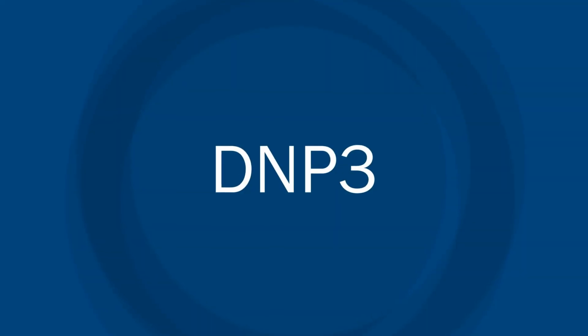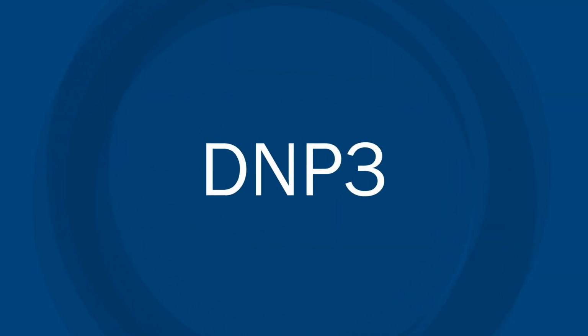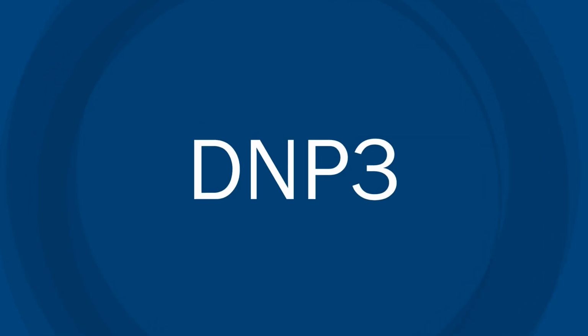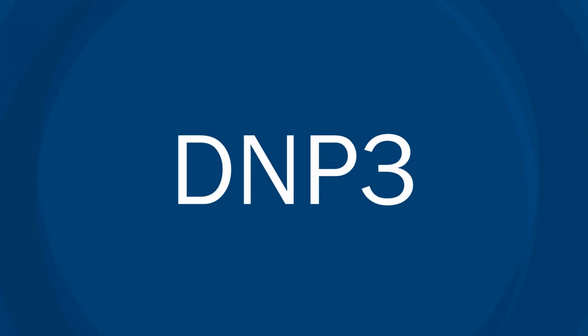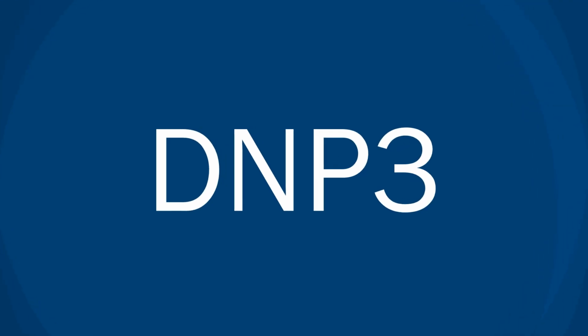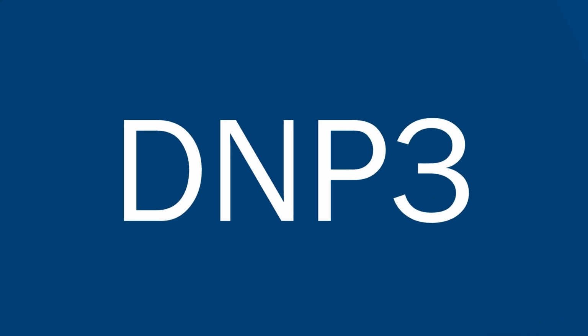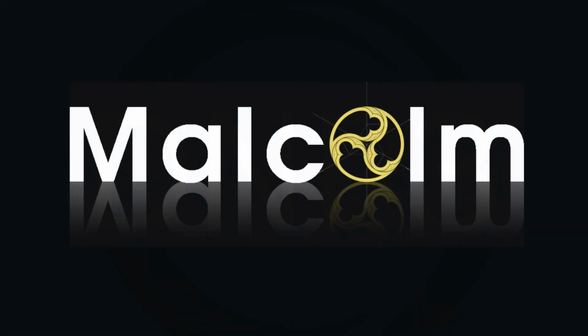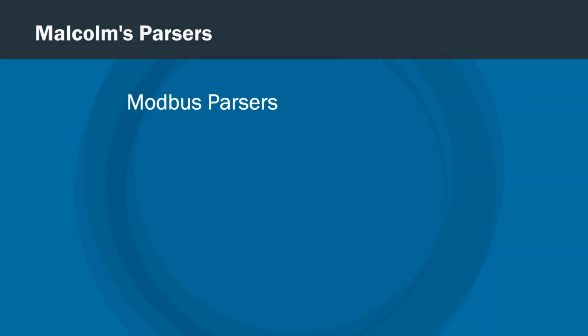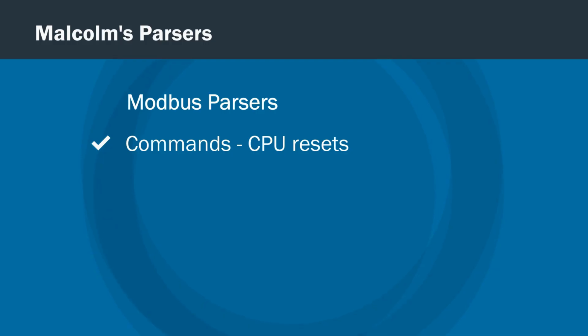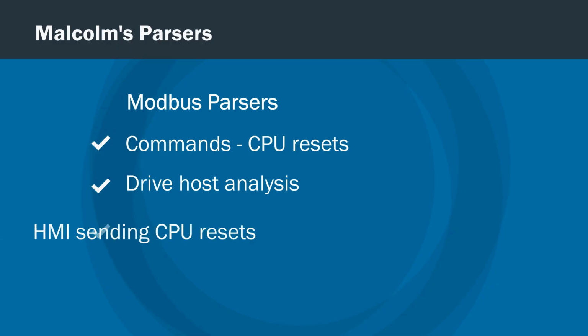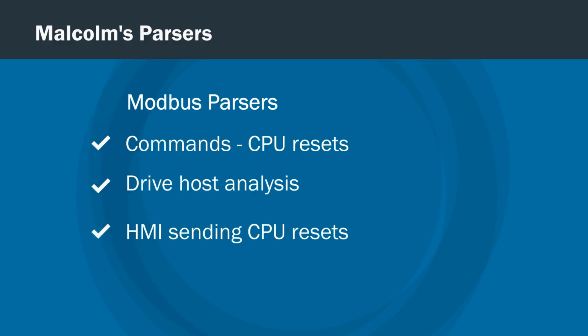If you observe OT protocols like DNP3 in the IT network, this indicates misconfiguration or inappropriate testing. Investigate the source, such as an engineering workstation that may be transient. Use tools like Malcolm's parsers to analyze protocol data. For instance, Modbus parsers can show if commands like CPU resets are being sent unexpectedly. Traffic from hosts within the network can be focused on if an HMI is sending out CPU resets.